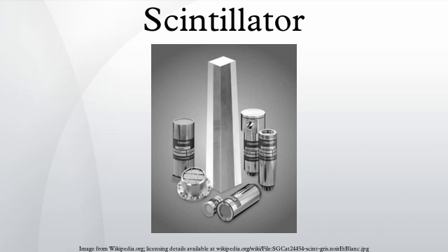Scintillation detectors are generally assumed to be linear. This assumption is based on two requirements: that the light output of the scintillator is proportional to the energy of the incident radiation, and that the electrical pulse produced by the photomultiplier tube is proportional to the emitted scintillation light. The linearity assumption is usually a good rough approximation, although deviations can occur.